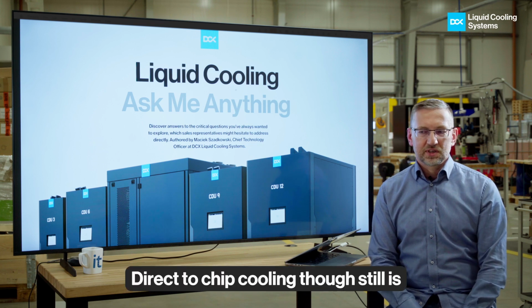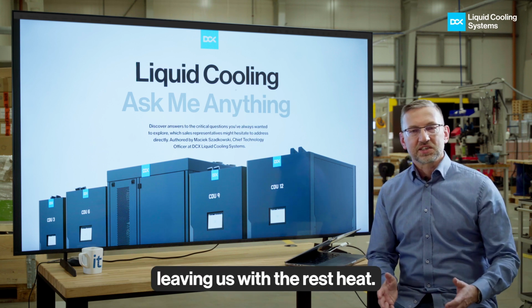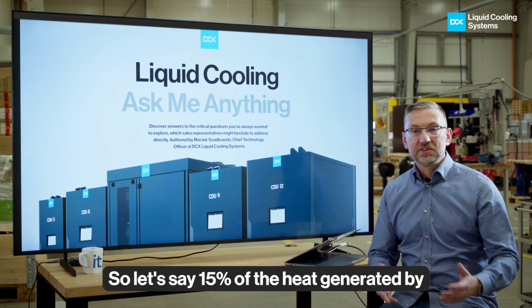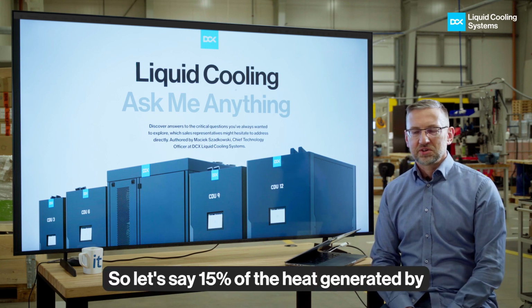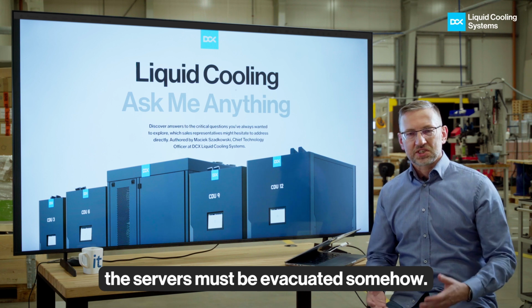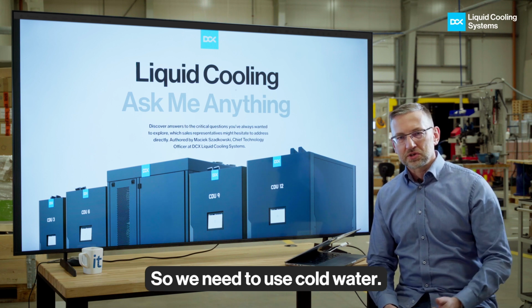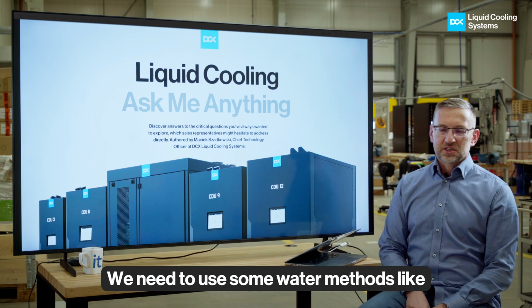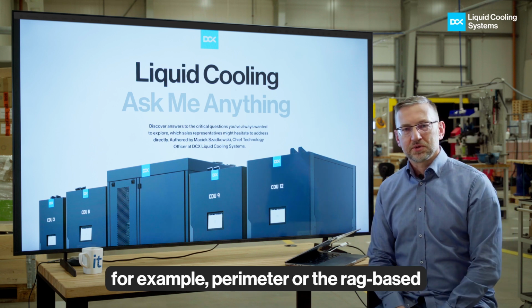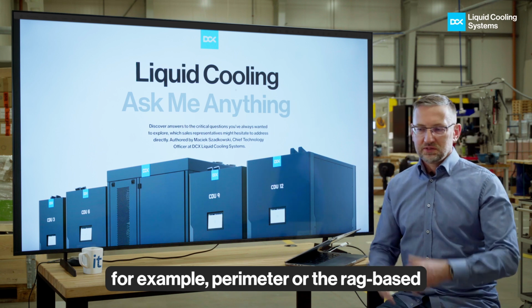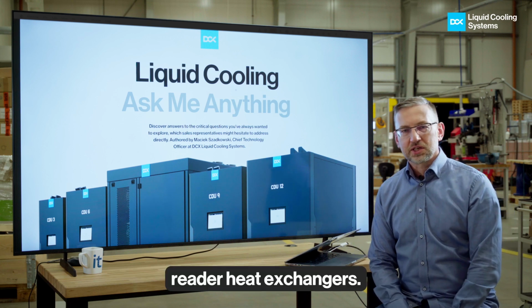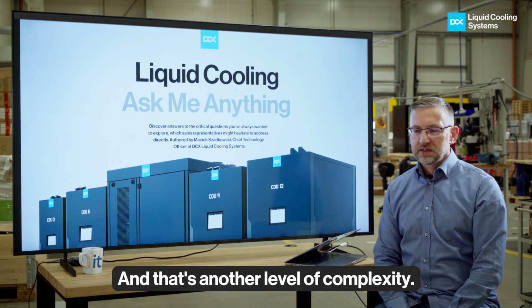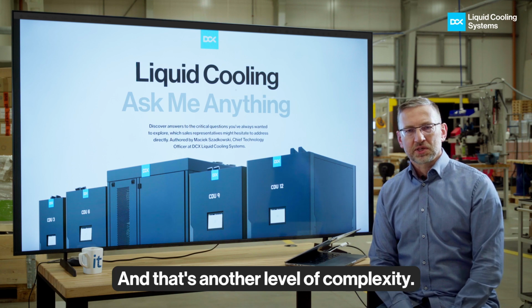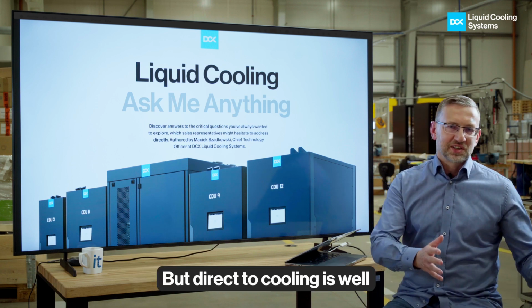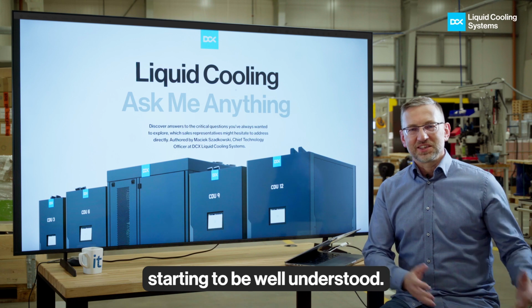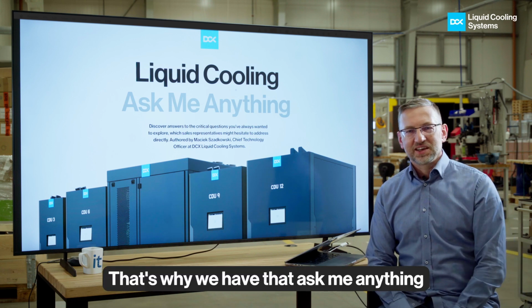Direct chip cooling, though, still is leaving us with the rest heat. So let's say 15% of the heat generated by the servers must be evacuated somehow. So we need to use cold water. We need to use some other methods, like for example, perimeter or rack-based rear-door heat exchangers. And that's another level of complexity. But direct chip cooling is, well, starting to be well understood. That's why we have that Ask Me Anything session.